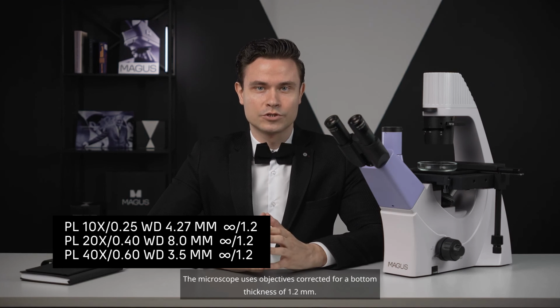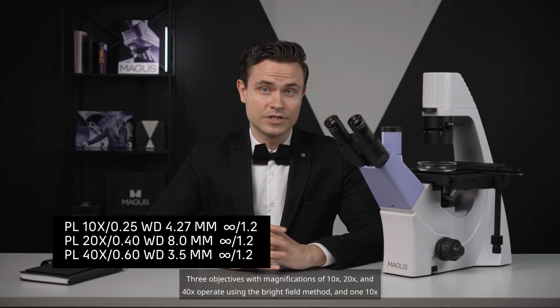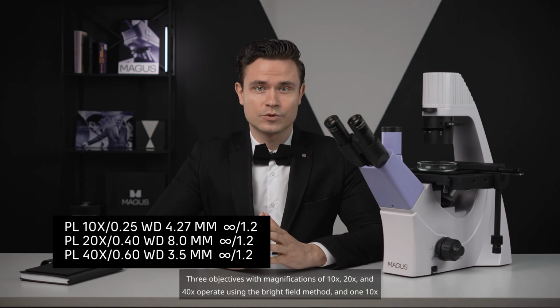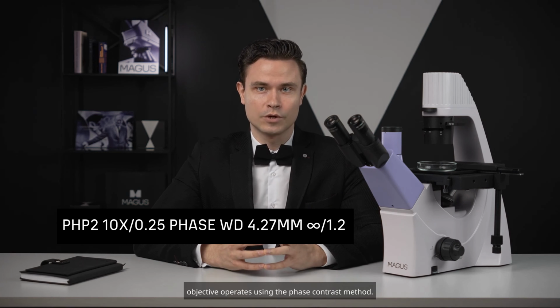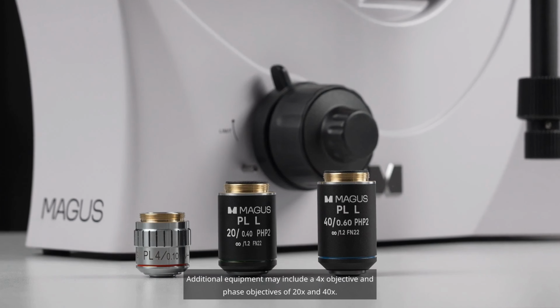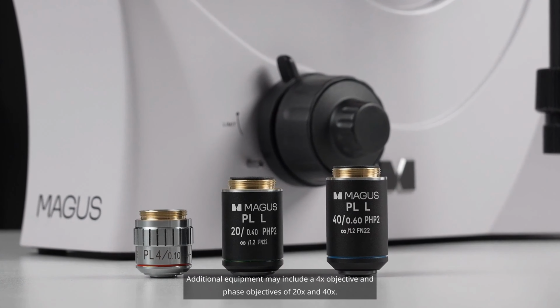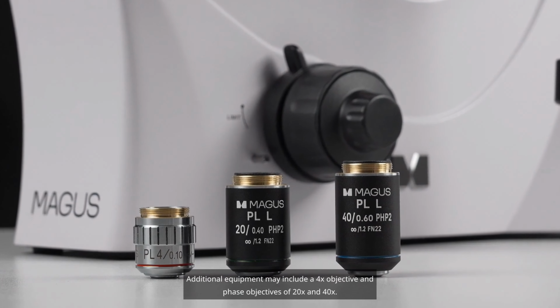The microscope uses objectives corrected for a bottom thickness of 1.2 mm. 3 objectives with magnifications of 10x, 20x, and 40x operate using the bright field method, and one 10x objective operates using the phase contrast method. Additional equipment may include a 4x objective and phase objectives of 20x and 40x.